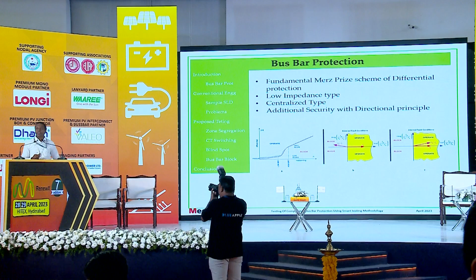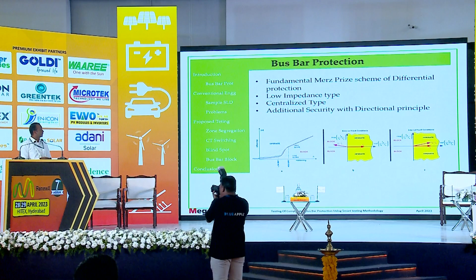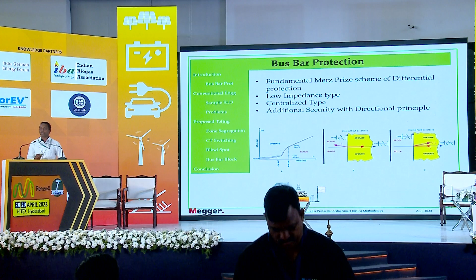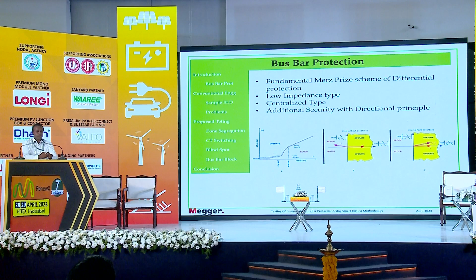That's the key principle. So here we follow the most fundamental scheme for differential protection, low impedance and centralized type. This is one of the popularly used differential protections, and additional principles are provided to ensure there is no misbehavior of the system. So that's the key behind this. For additional security, we have principles such as the directional principle or rate of change of restraint to ensure the system is properly tuned.